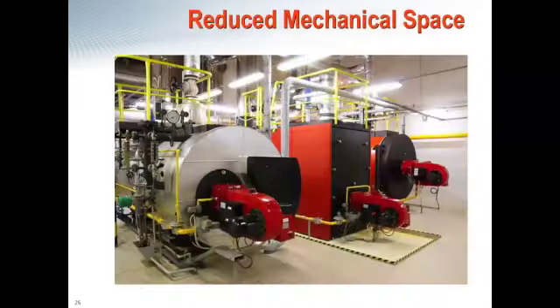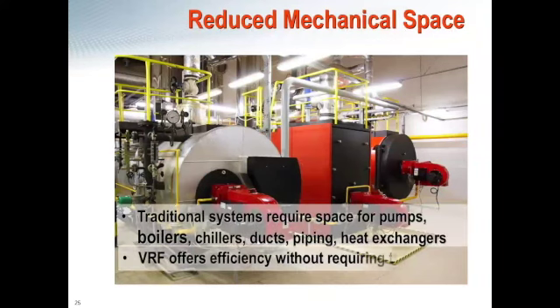Moving along, a lot of the applications I see are conversions or retrofits from these traditional chiller boiler systems. One thing is weight. They're about 30% heavier, but they're also significantly larger, and as I said earlier, they need to be centrally located. So when you're able to split out the total load and move your condensing units to where it's most advantageous for the building, you can reclaim a lot of mechanical space that is typically used for that existing chiller boiler system and repurpose it into something that the building owner can actually monetize. So rather than having a massive chiller boiler plant in a building, you can eliminate that, go with an air source or a water source VRF system, and then retrofit that into any kind of amenity space that might be valuable to that owner.